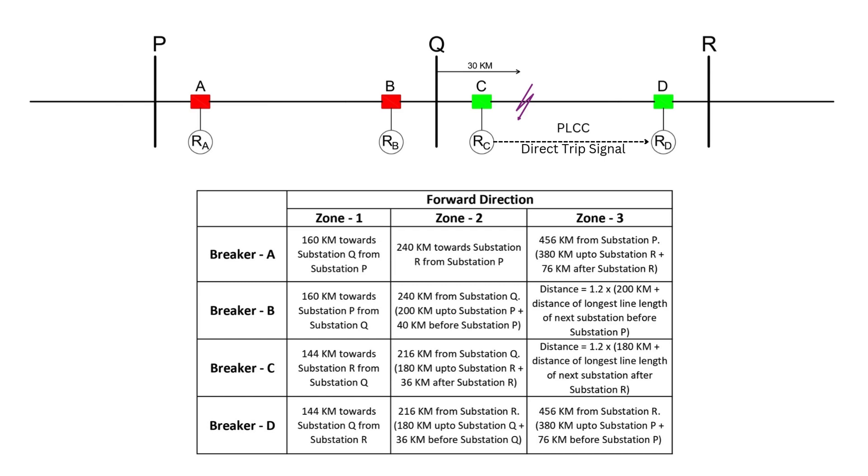Relay A will also detect this fault within its zone 2 range, but since the fault is cleared by breaker C, breaker A won't trip unless the fault persists for 350 milliseconds. Relay B will not respond as it is a reverse zone fault.